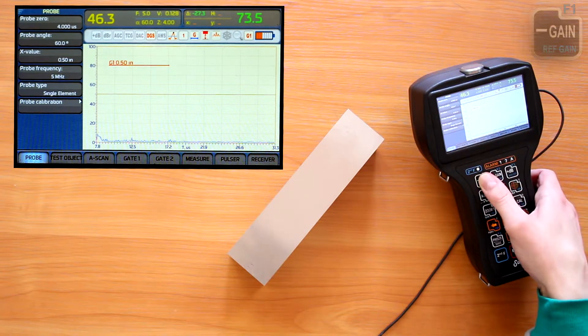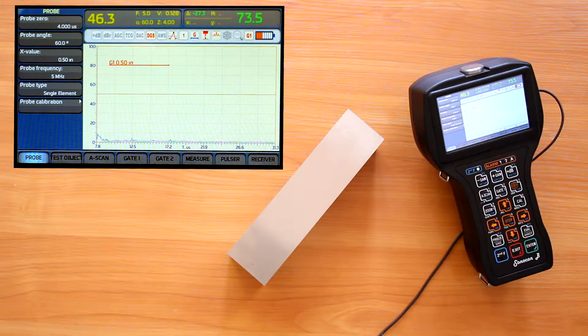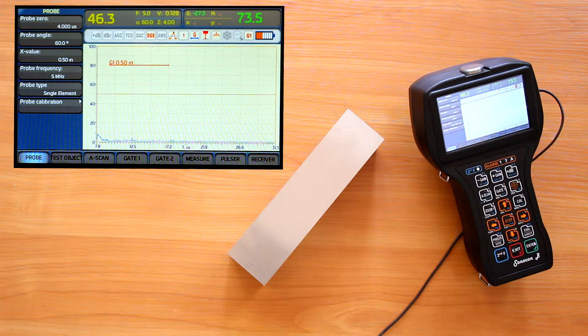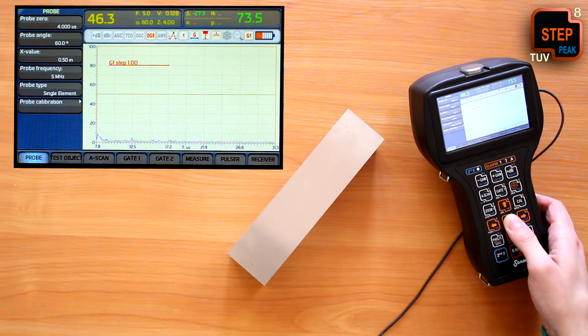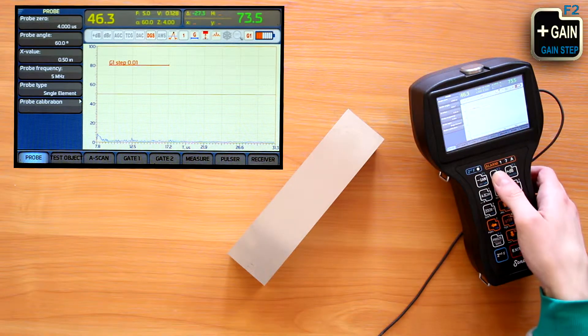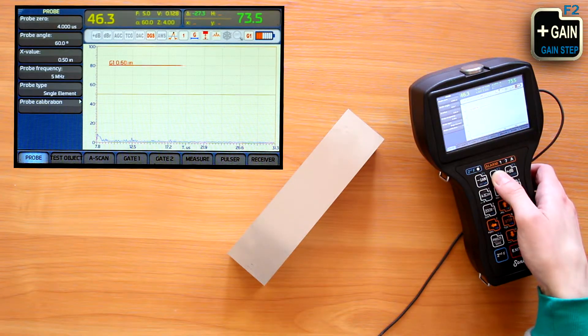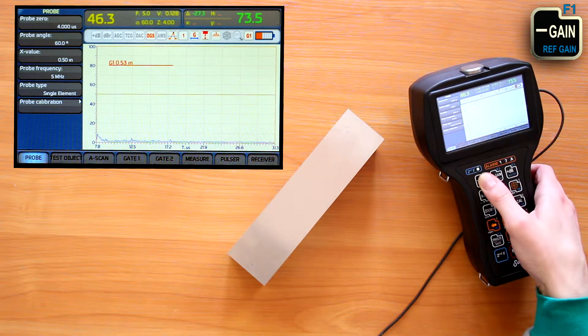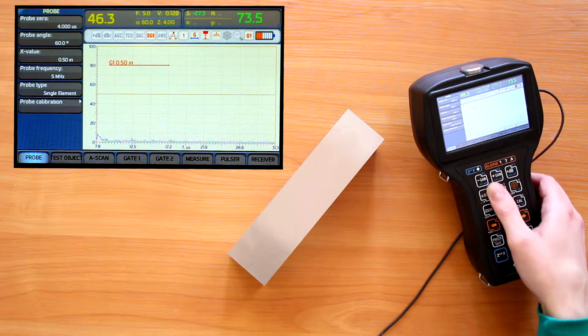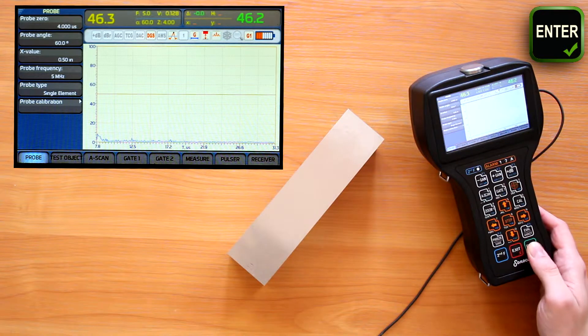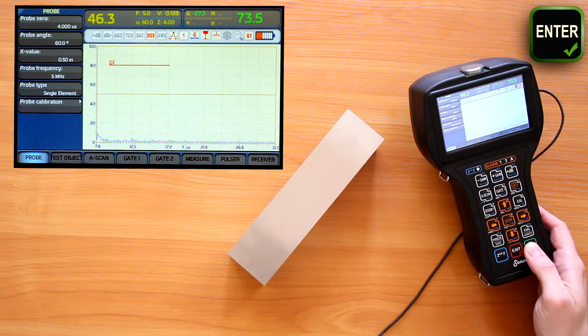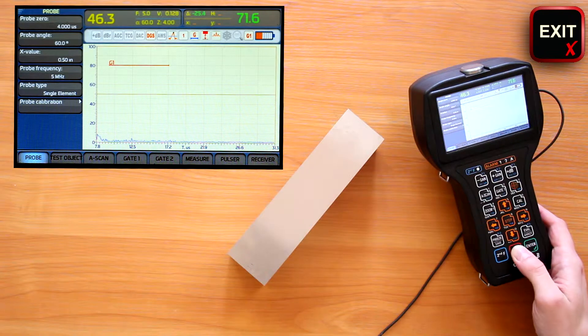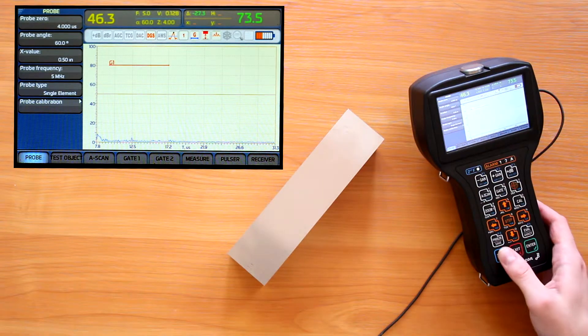When changing one of the gate parameters, the step button would cycle its increment-decrement step. Enter button would switch the gate on and off. To exit the first gate direct control mode, we can press exit button.